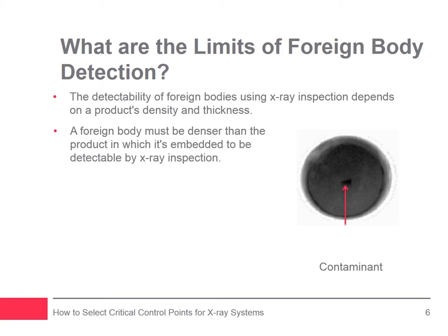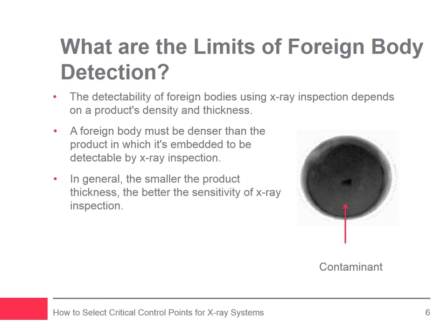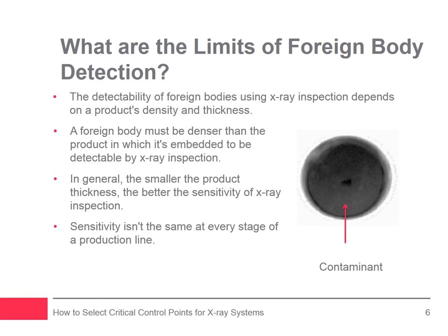A foreign body in a shallow layer of product in a bulk flow production line — for example cereals or frozen berries — is easier to detect than a foreign body hidden inside a finished, sealed pack. In general, the smaller the product thickness, the better the sensitivity of x-ray inspection. Many other factors can affect the sensitivity of an x-ray system, and sensitivity is not the same at every stage of a production line. Some locations are better than others for detecting certain foreign bodies.